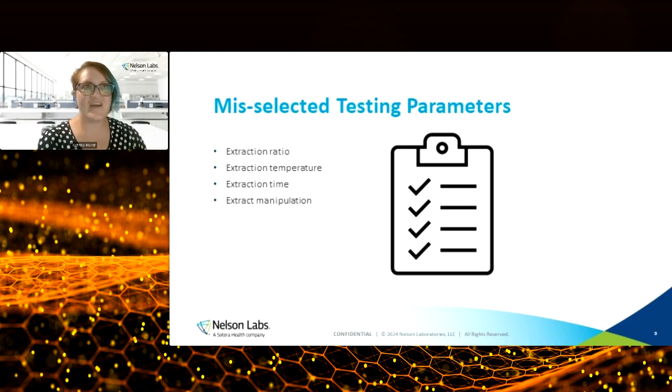Okay, so another very common issue that we run into when we're helping sponsors with FDA or other regulatory body feedback is that the regulatory body doesn't accept the parameters that were used in the testing. And again, when you're sending in your samples, you will select your extraction ratio, you'll send in the surface area and the temperature. You're selecting these in the sample submission form. So knowing how your device should be tested and what extraction temperature time ratios should be used for your device is vital. If you tell us to do it one way, that's what we're going to do in the lab.